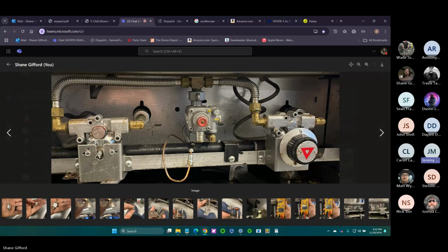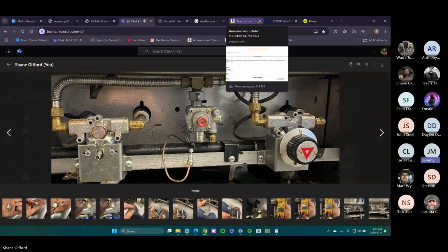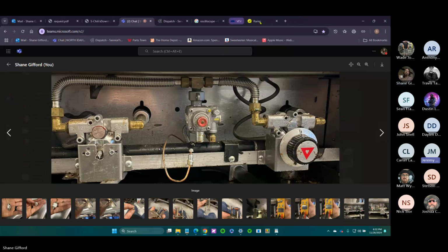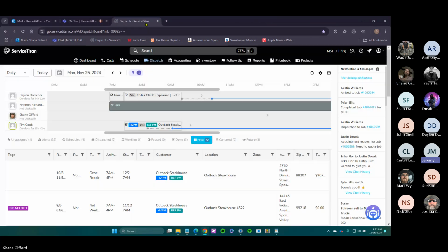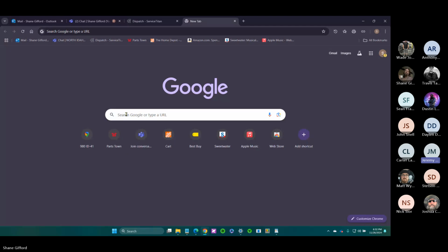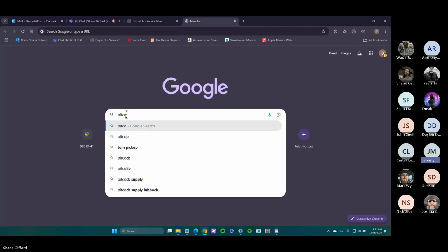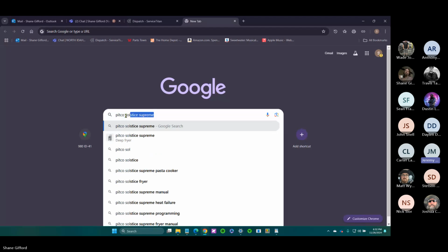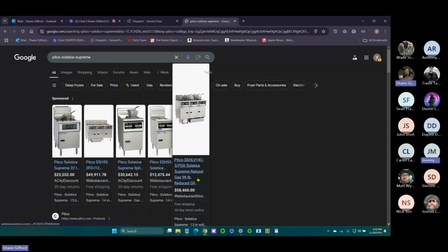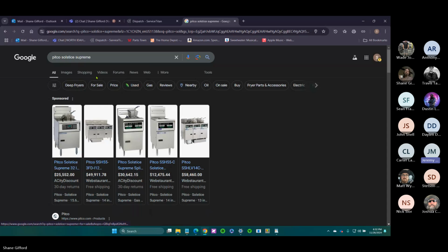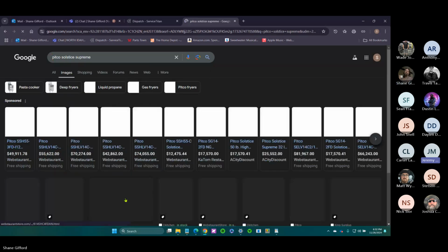This wasn't at a Five Guys. It was at a Buffalo Wild Wings, and they use Pitcos, but they use the Solstice Supremes, and their solid state controls are a little different than the ones at Five Guys. The ones on the Solstice Supremes, at like a Chili's maybe, or a Buffalo Wild Wings, have a manual and an auto mode, whereas the ones at Five Guys do not. If you have it swapped to manual, it will not allow the solid state control to automatically determine temperature, things like that. They have to set it all manually.